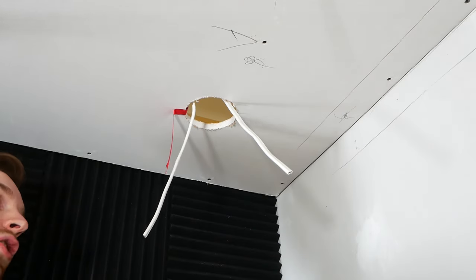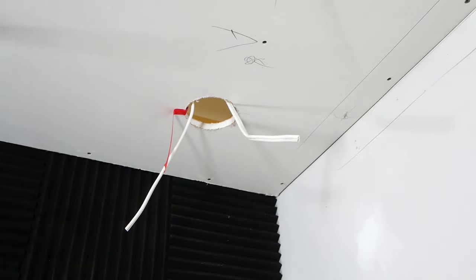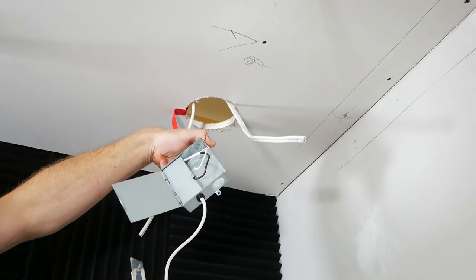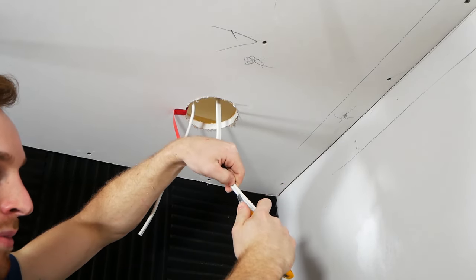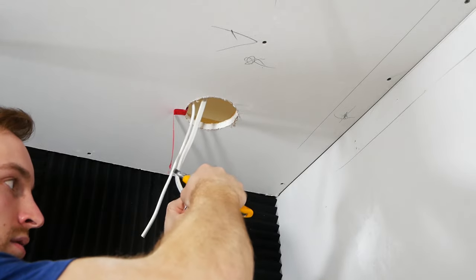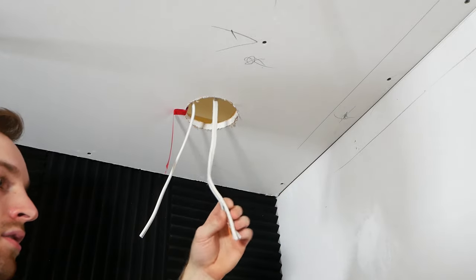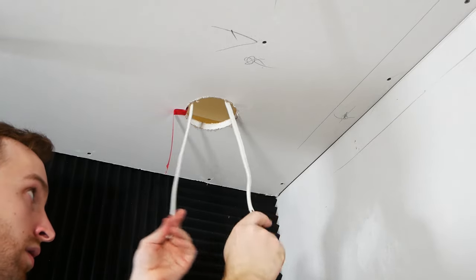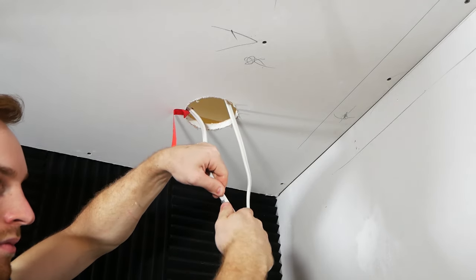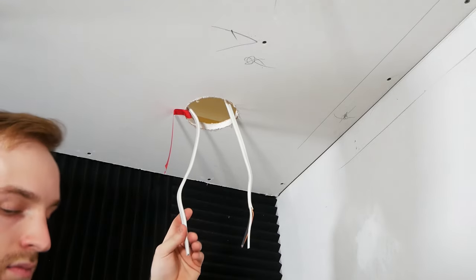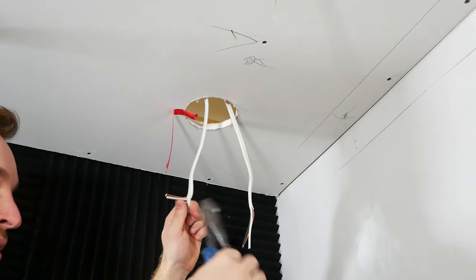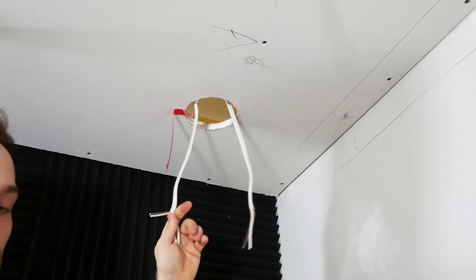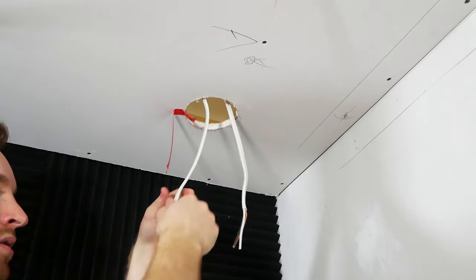To install our recessed lights first we must strip our wire. Because the drivers that we're going to be using, they have such a small amount of space to make the connections, we don't want to strip the wire too much, I only like maybe three inches worth. I'm just going to take my knife, pierce the Romex, strip down, and then going to lightly, very lightly, score my Romex and I can just pull that right off. I'm going to do the same with the other one. If you don't want to score it, you don't have to. You can just peel it up, take some side cutters, and cut it right there, and that's fine. Nothing wrong with that, but this is just cleaner.